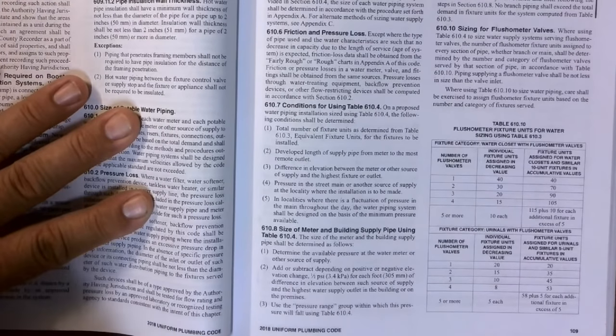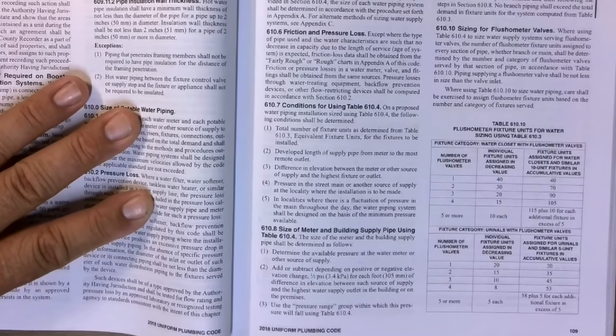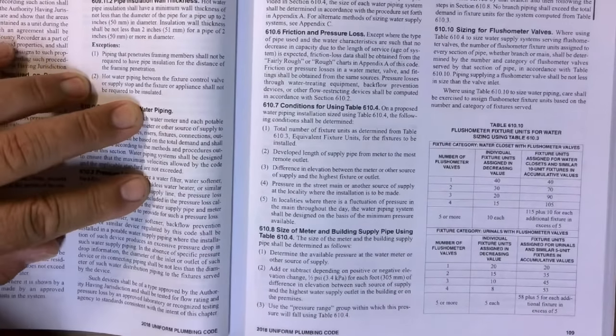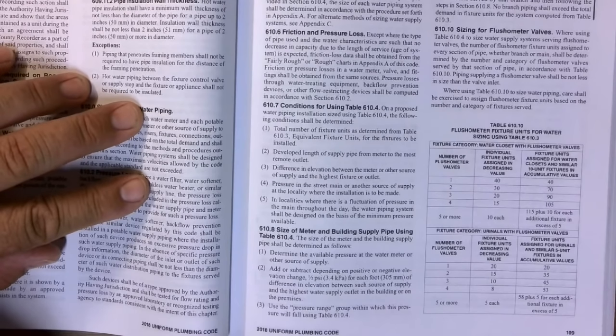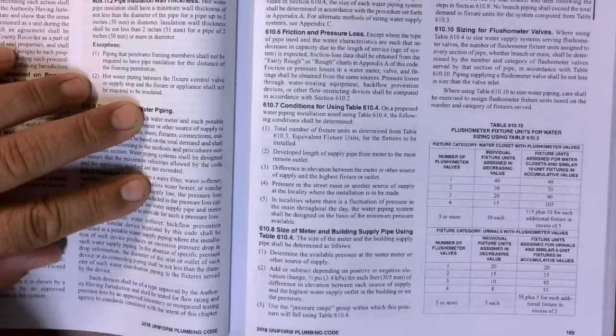Section 610.7, the conditions, and we'll scroll down here for a sec. So now the conditions for using 610.4. On a proposed water piping installation sized using 610.4, the following conditions shall be determined. Number 1, total number of fixture units is determined from table 610.3, their equivalent fixture units for the fixtures to be installed. Number 2, developed length of supply pipe from the meter to the most remote outlet. So that's your total distance. In distance, you lose pressure. So they already have all that figured out for us. We need to know which chart to utilize, and when we get there, you'll see.